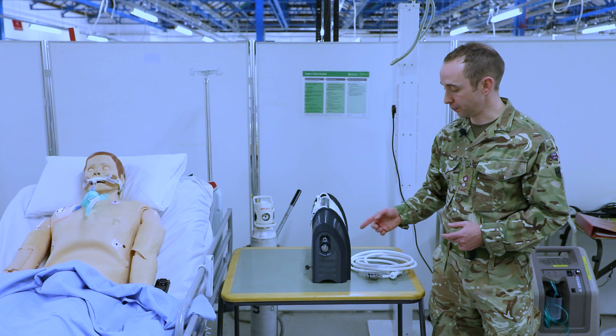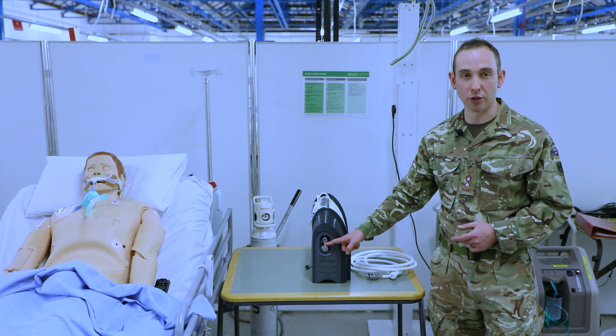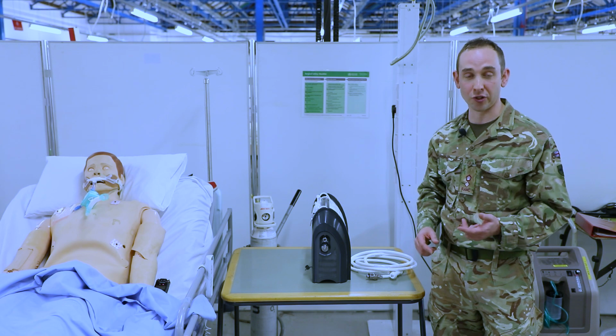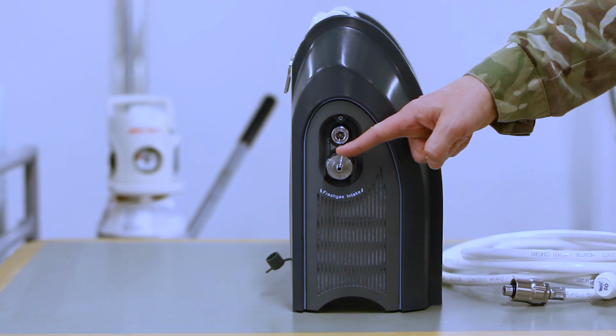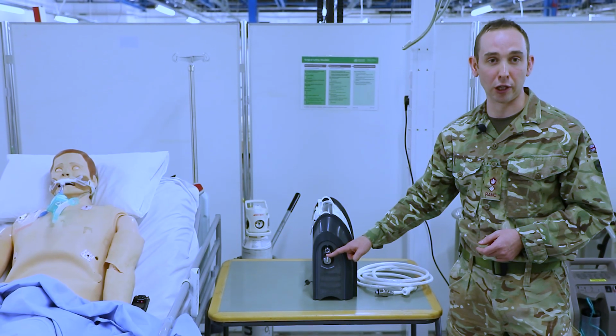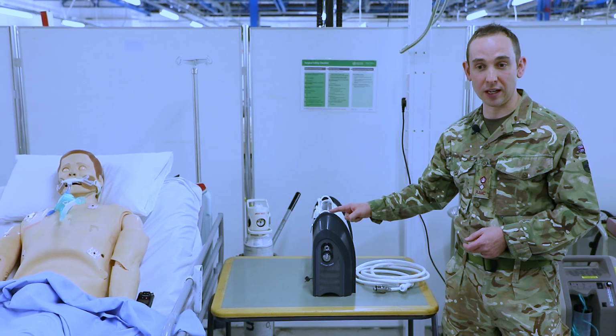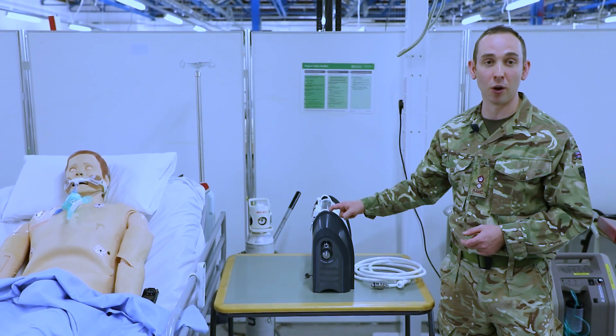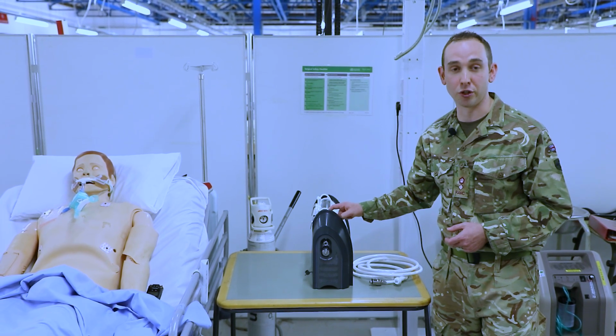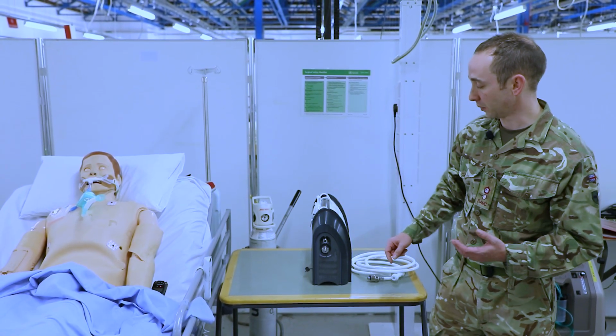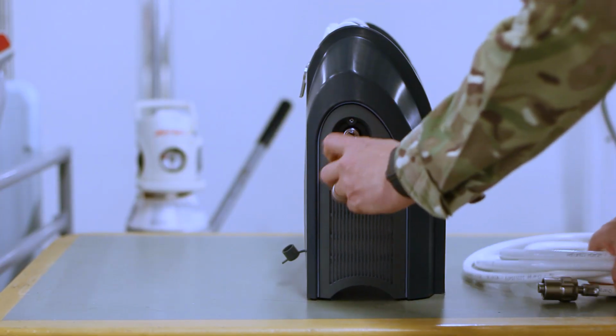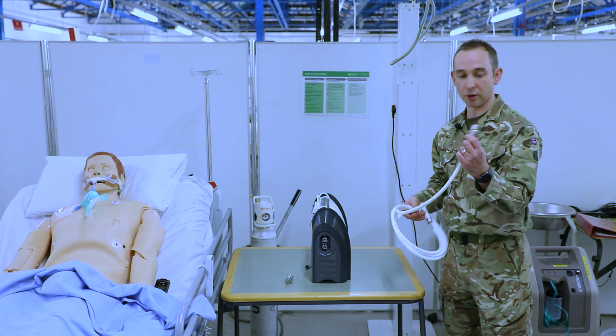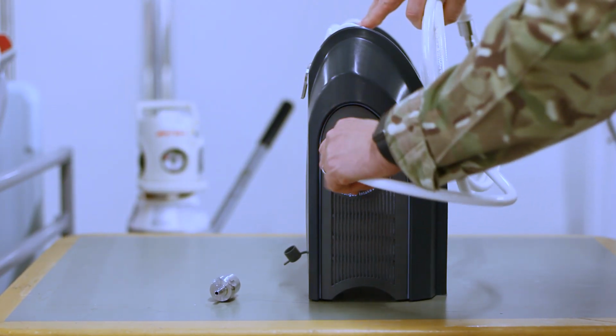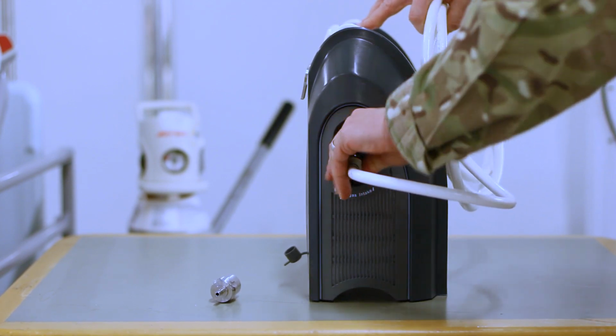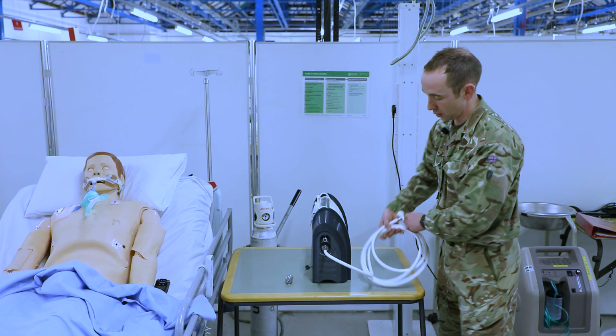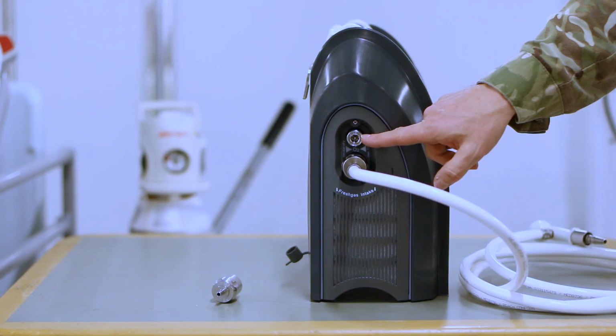There are 3 ways of delivering oxygen. Firstly, using the low pressure adapter, you can either use an oxygen concentrator or an oxygen cylinder using some bubble tubing onto the low pressure oxygen adapter. It's important though that when you're using the low pressure oxygen that you set in your settings that you're using low pressure oxygen, and if you are using the oxygen concentrator that you do tell it that you're using oxygen 93 or 93% oxygen. If you're not going to use low pressure oxygen, you'll be utilising the high pressure oxygen hose, and you'll then swap this onto the lower connector using the non-interchangeable screw thread, and then attach this using your Schrader valve. There is also on this machine a quick coupling device, but it is not in use in this country.